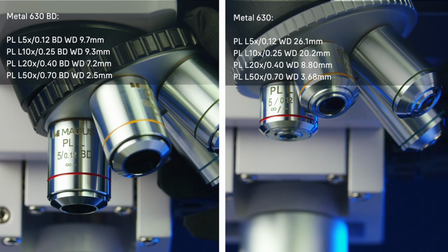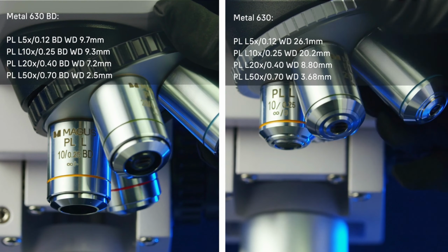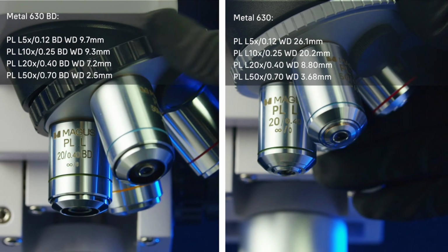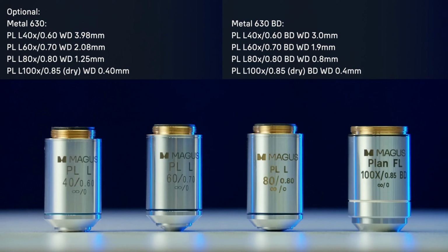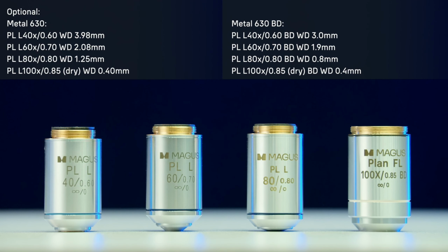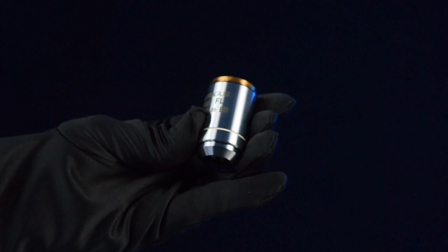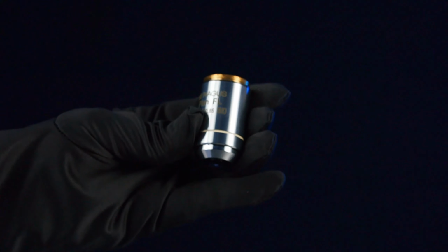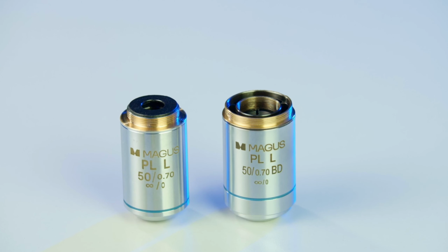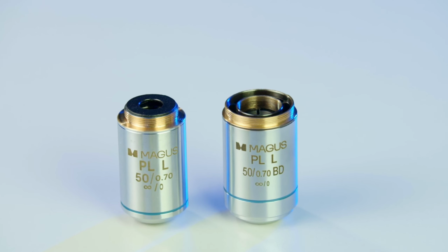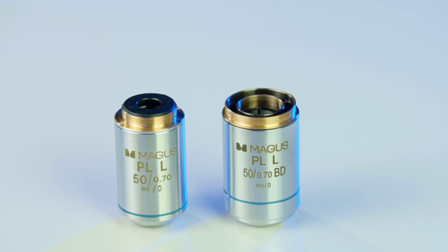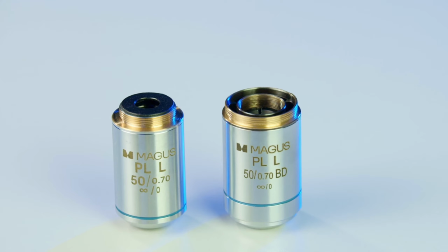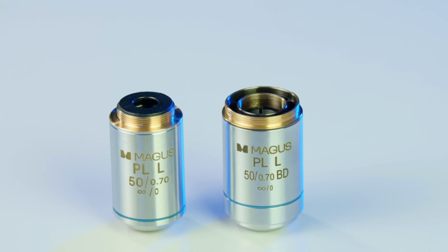The microscopes are equipped with objectives of 5, 10, 20, and 50 times magnification. Additionally, objectives with 40, 60, 80, and 100 times magnification are available. Please note, microscopes operating in dark field mode are equipped with special objectives. Objectives marked BD have an annular gap between the optics and the housing. The mounting diameter and thread of these objectives differ from models designed only for bright field. Therefore, when choosing additional objectives, it is important to consider compatibility.